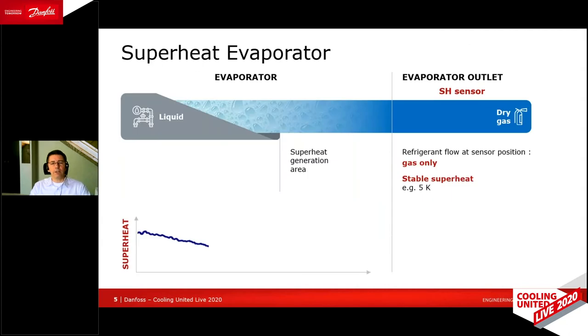Here's an explanation why that is. Looking at an evaporator, it is filled with a mixture of gas and liquid that evaporates inside. At the end of the evaporator, we have an area where we generate the superheat — gas leaves the evaporator as dry gas, with a stable superheat of, let's say, 5 Kelvin. The blue curve shown is the superheat measurement.